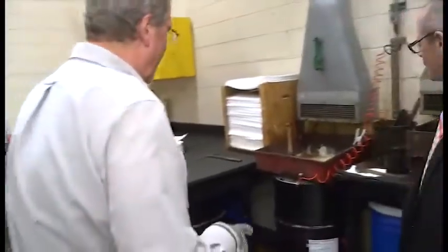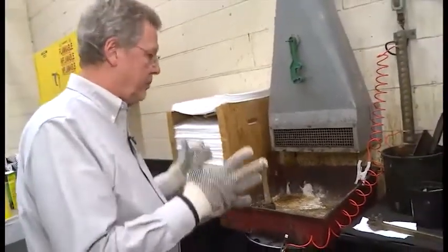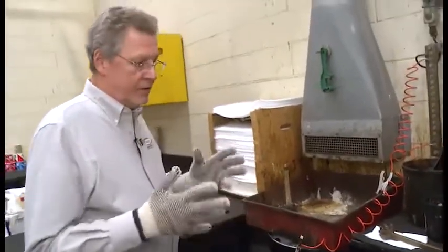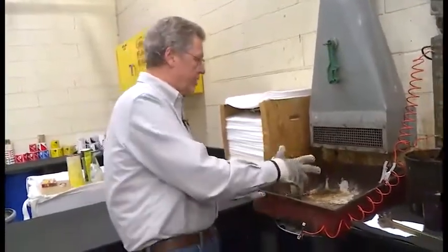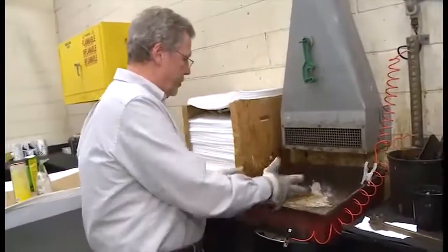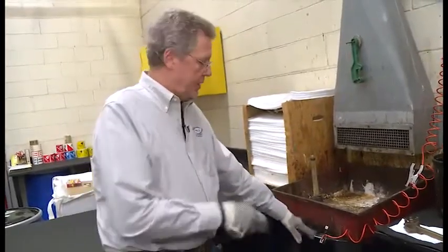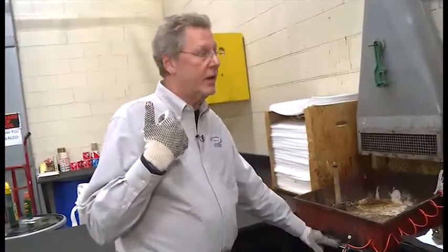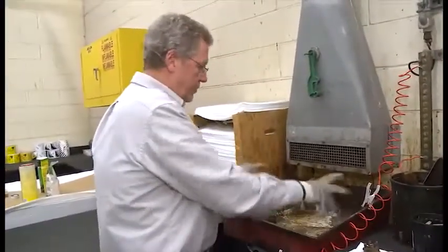Another product we pour out of containers is flammable liquids. Because we have flammable product around here, we have to put grounding straps and bonding straps to the container. We have a lot of boat owners in Lake County who want to get rid of their gas at the end of the season. We'll take their container, pour it off into a 55-gallon drum, and give them their container back if they wish. The drum is topped and secured, then shipped out for fuels blending. We have ventilation hoods pulling air across the work area so there's no vapor accumulation and no need for respiratory protection.